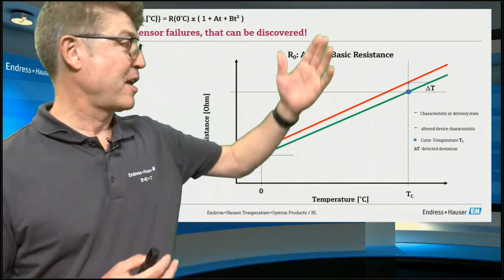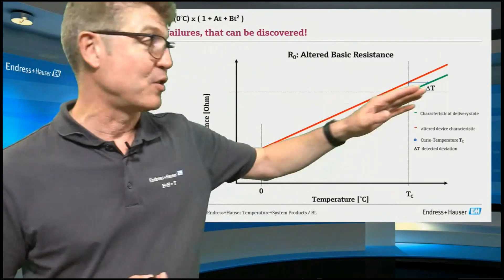And the other way around, if it's good at the Curie temperature, and all of the risks affect the entire curve, I personally have no idea how it could be bad at any other temperature if it's good at the Curie temperature. That is the basic principle of the one-point calibration. It is too long to explain it to the auditor, I think. So our recommendation is you won't stop manual calibration, but you can easily extend the intervals according to the rules of the FDA to 2, 3, 4 years or something, and the rest is done automatically. That is a new approach in the calibration we would like to offer you today.